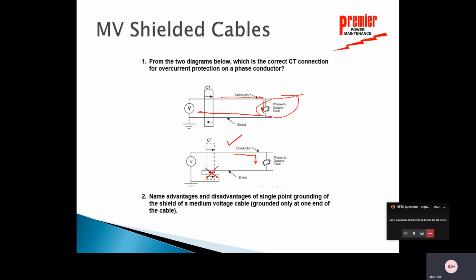Now, advantages and disadvantages of multi-point grounding, where I would have the shield grounded at both ends. The advantage is, since it's grounded at both ends, no shield voltage can be present, so it increases safety there. It provides protection against both capacitive coupled and inductively coupled induced noises, so I have more protection there. Disadvantage: since the shield is connected to ground at both ends, the current induced in the shield now has a closed path. So it has a return path, and that current varies with the load on the main cable. It could increase cable heating. Derating of the cable could be required.